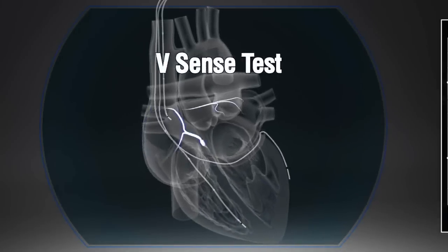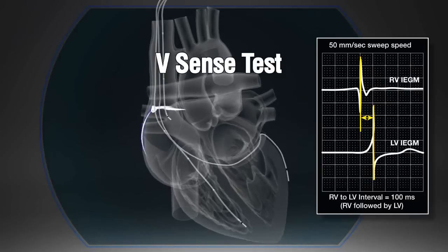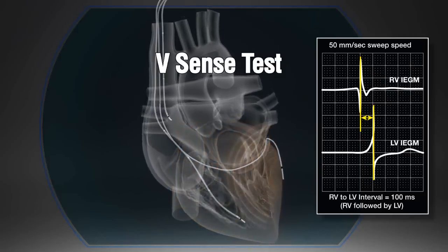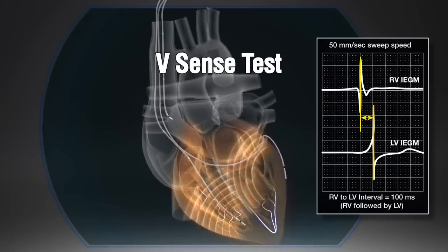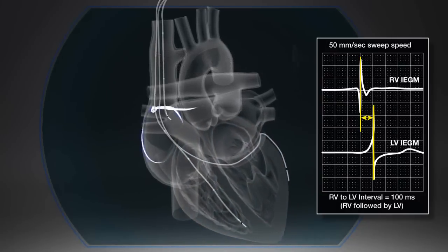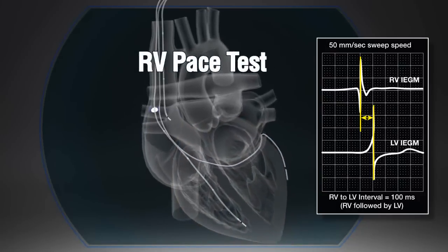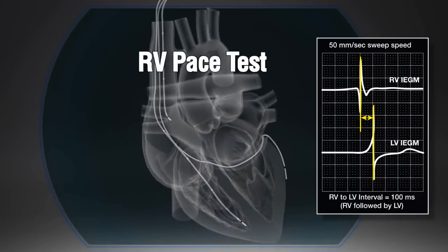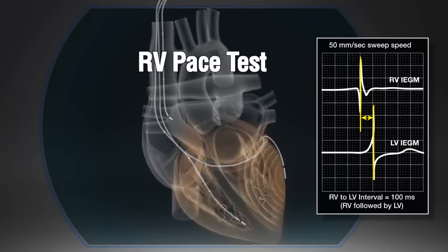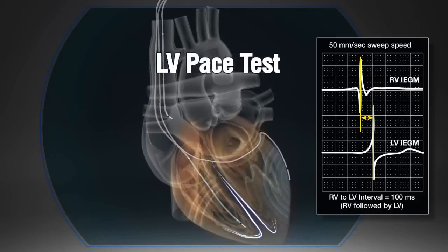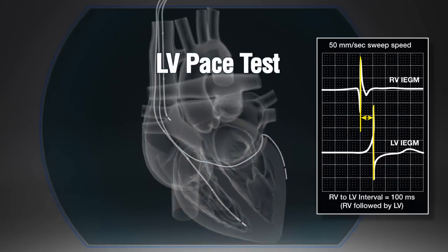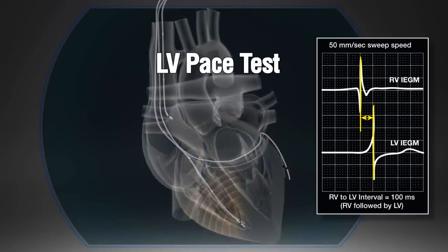VV optimization is calculated based on three measurements: V-Sense, RV Pace, and LV Pace. The V-Sense test measures the intrinsic delay between the right and left ventricles. The RV Pace and LV Pace tests are then used to compare the difference in conduction speeds. These three tests together characterize inter- and intraventricular conduction properties and recommend the optimal VV delay. The goal of VV optimization is to time right and left ventricular activation so that the paced wave fronts meet at the ventricular septum.